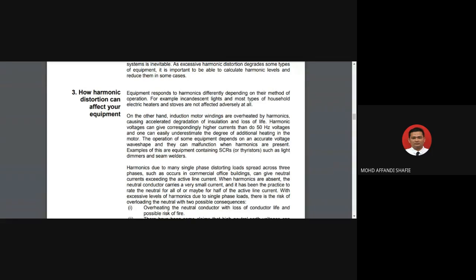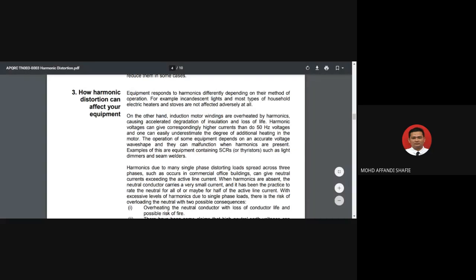Effect kat sini. But on the other hand, apa yang berlaku sekarang ni apabila harmonic level tinggi, induction motor windings are overheated by harmonic. Overheated lah. Overheated by harmonic, causing accelerated degradation of insulation and loss of life. So harmonic voltage can give correspondingly higher current than do 50 Hz voltage, and one can easily underestimate the degree of additional heating in the motor. So higher current. Okay.